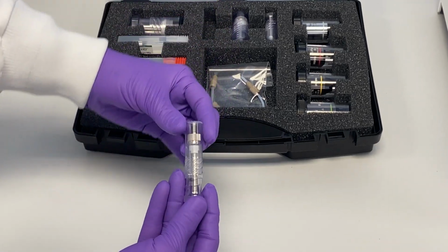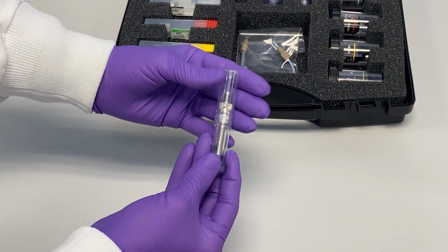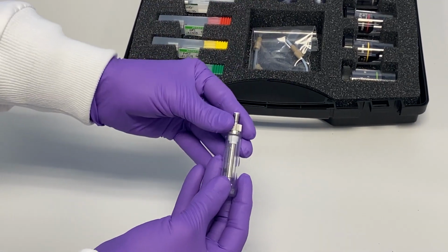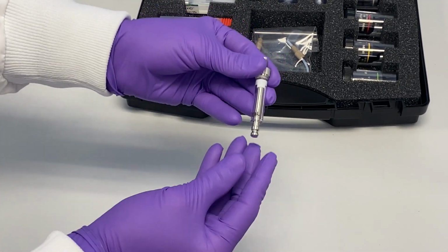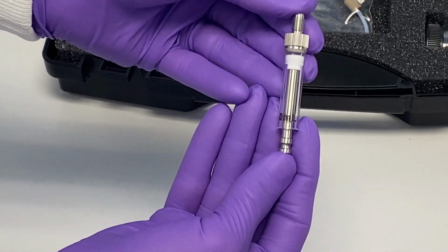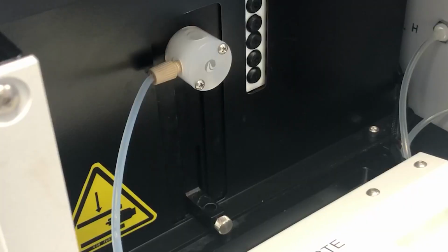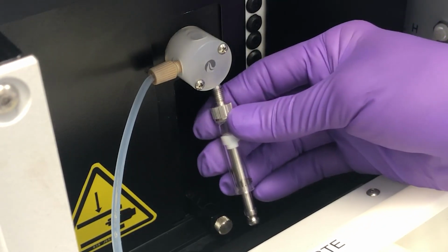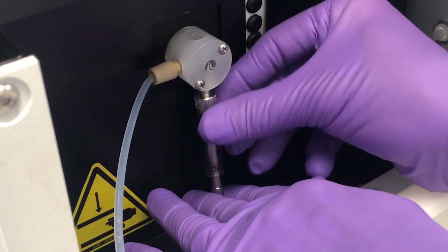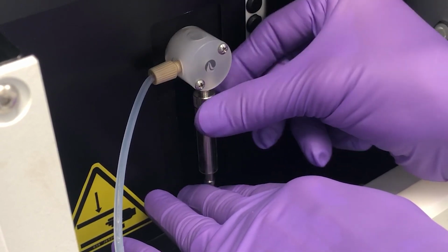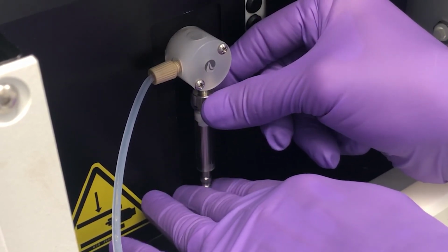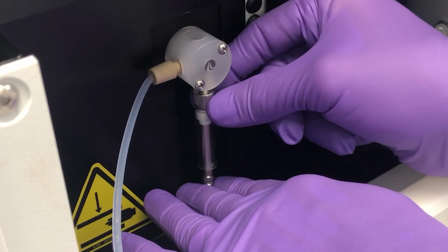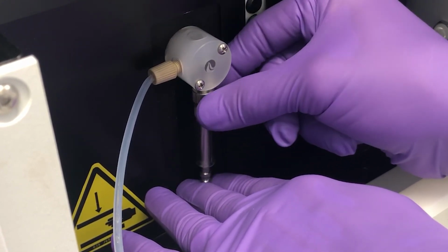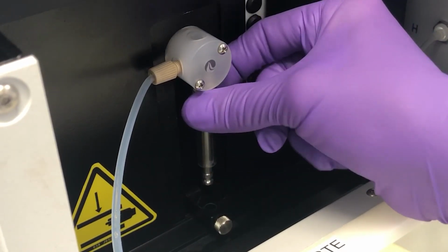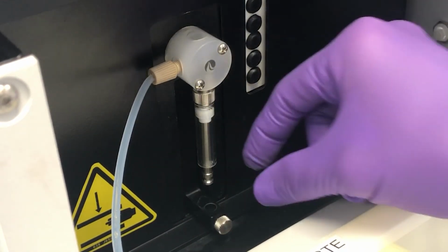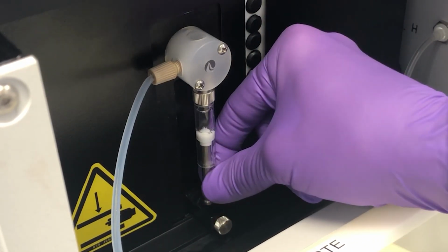Remove the syringe from its protective case and confirm the syringe volume by checking the label printed on the syringe barrel. To install the syringe, hold the syringe by the syringe barrel screw and carefully align the screw with the threaded hole at the bottom of the pump manifold. Using your other hand to stabilize the syringe alignment, continue to screw the syringe into the manifold until securely tightened. Then, carefully draw the plunger arm and fully seat the plunger head into the pump arm socket.